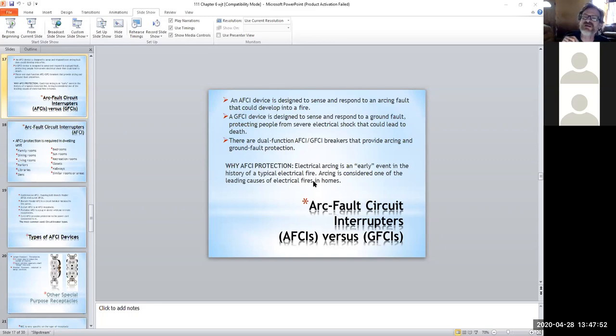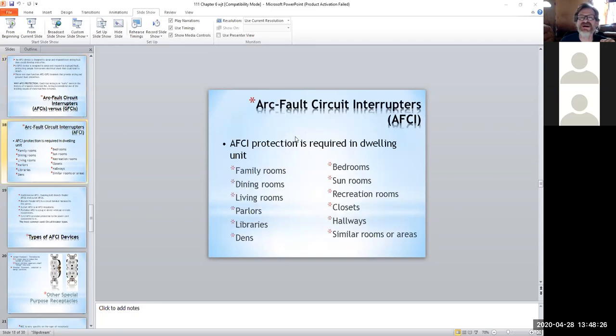I've seen it happen a couple times, and it's not quite enough to trip the breaker because it's not staying consistent. But if it's on a carpet area or flush against the couch or some fabric, it'll light it up. And the crazy thing is, even while it's burning through the insulation, the circuit breaker won't trip. It'll continue to feed that, so you'll still get arcing happening, and next thing you know your front room's on fire.